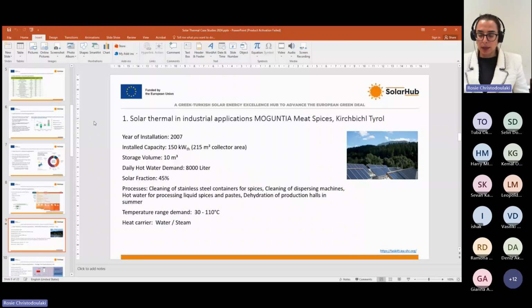So let's start with the first case study of industrial applications, and this is Moguntia meat spices in Tyrol. It was installed in 2007 with a capacity of 150 kilowatts thermal. That corresponds to 215 square meters of collector area. It has a heating storage volume of 10 cubic meters, and it can produce a daily hot water of 8,000 liters with a solar fraction of 45%.